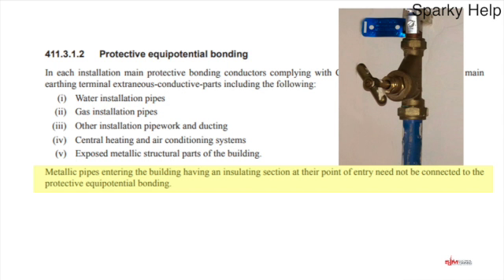If you can guarantee that no other metalwork beyond this point that we're looking at now actually goes into the ground, because if any of it goes into the floor screed, so the copper pipe goes into the floor screed, and I know it would probably be covered with material to stop it being damaged, but if you're not sure and it goes into contact with the ground, then you would need to put a bonding clamp on it. So you still might see people just do it because it's just easier to do it rather than trace out the rest of the building to see whether it does actually go to ground.